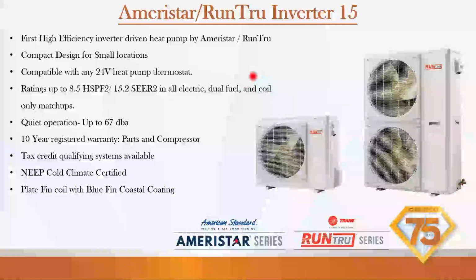Here, let's do the red. There we go. So coil only matches, so really it doesn't care what furnace you're putting on there. Of course, we want to make sure that we've got the 400 CFM per ton, and we're matching the airflow up per tonnage. It's a pretty quiet unit, 67 dBA, 10-year registered warranty.